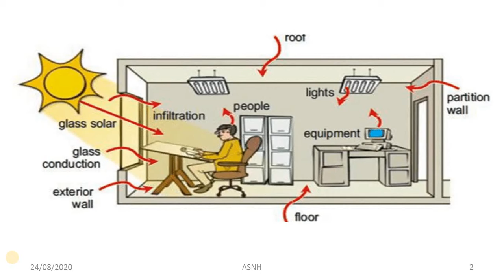So students, the most important part: there are two basic ways through which we can calculate that heat load. The first method is the manual process. In that, the data gathered from the building survey and complementary documents is analyzed using prescribed equations and tabular format. The exact equation and the table values of the U values are determined based on the building geometry. Also, we need to calculate various U values, that is, the overall heat transfer coefficient. We must also calculate the latent and sensible heat factor with the help of some standard assumptions, and we must carry the ISHRAE, ASHRAE and Carrier handbooks in order to find the various values.